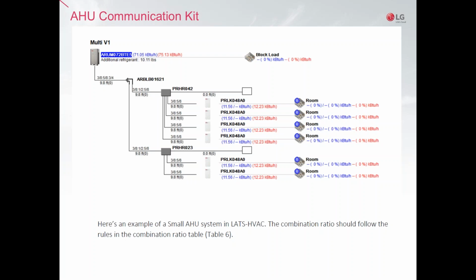One of the tools we use for selecting equipment is our own LATS HVAC software, which is a very easy platform to design any VRF system, including those with AHU kits. In this case, we selected the smallest three-phase size, a 6-ton unit, ARUM072BTE5, which is a 2A three-phase unit, and connected it in a heat recovery configuration. You see a line coming out of the outdoor unit, which notes the piping diameter and a random length. Every length in this drawing has the same 9.8 feet.